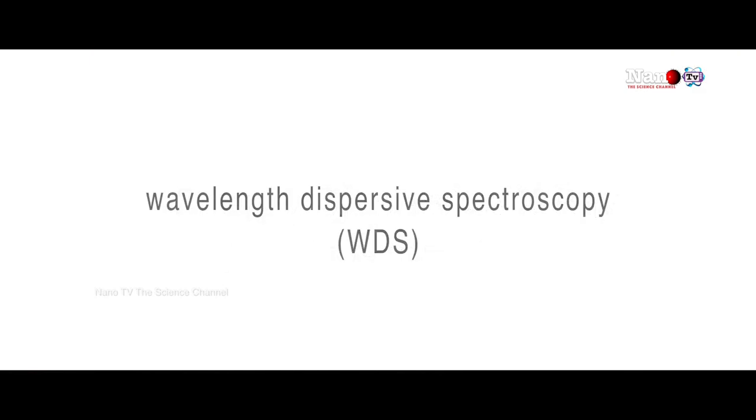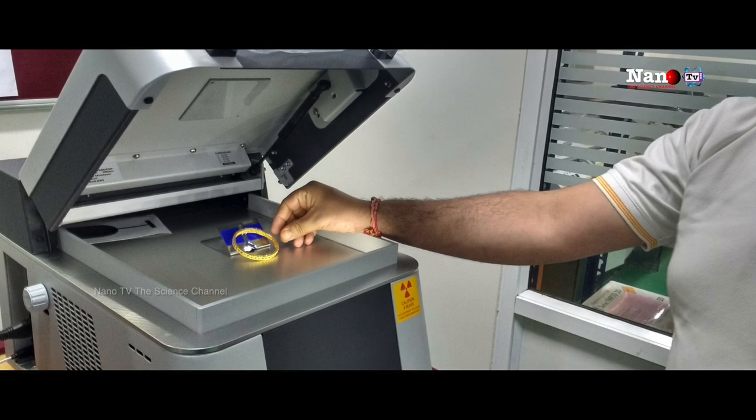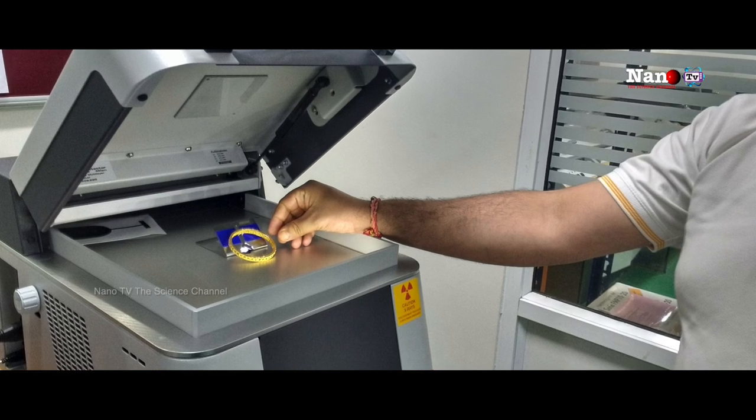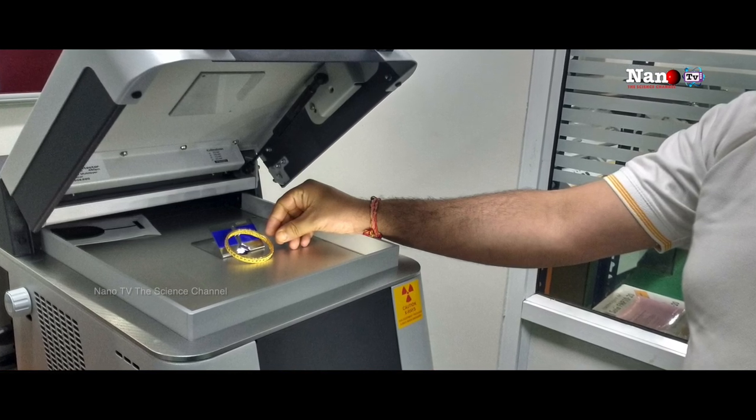You can also do different types of analysis in the scanning electron microscope because X-rays are generated along with the sample interaction. X-rays can be analyzed using different detectors — this is called EDS or WDS. EDS stands for Energy Dispersive Spectrometry, where electrons interact with the sample and the excess energy coming out is detected using a relatively cheap detector to find out the energy value and identify the elements present.